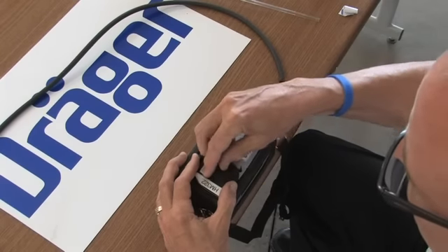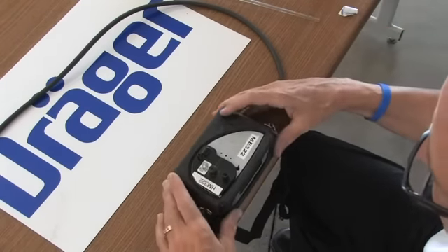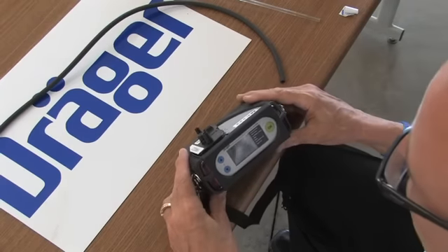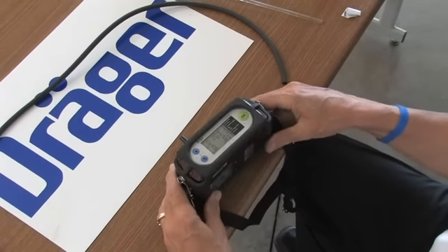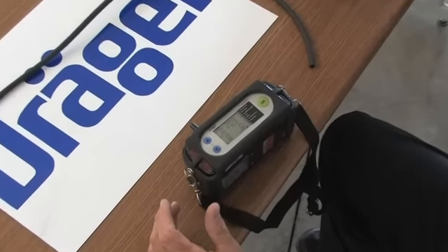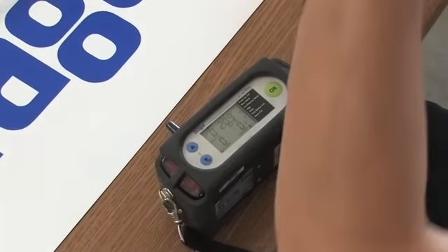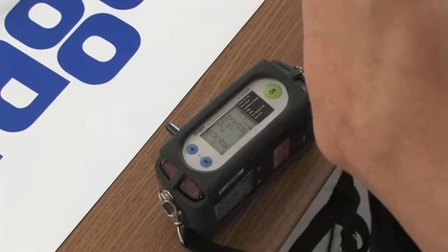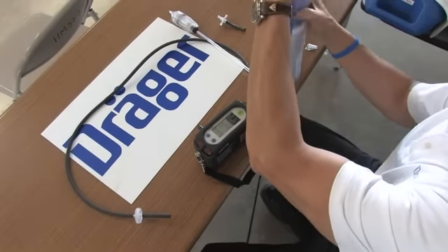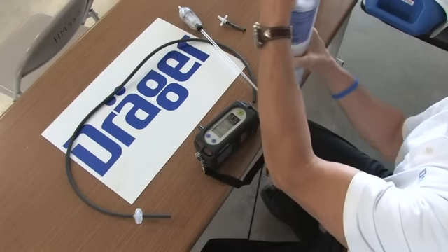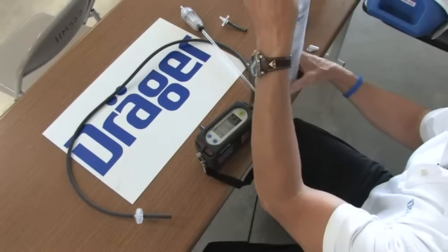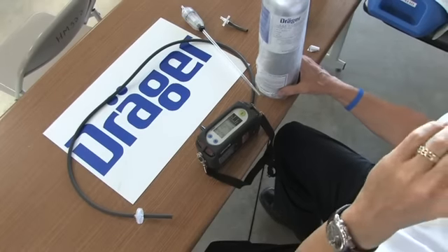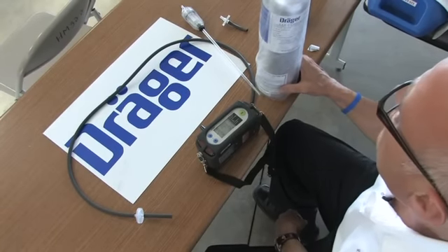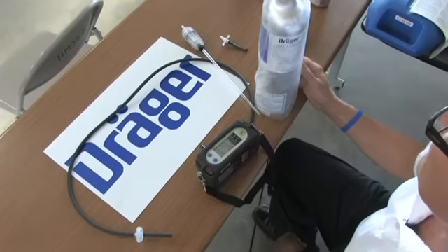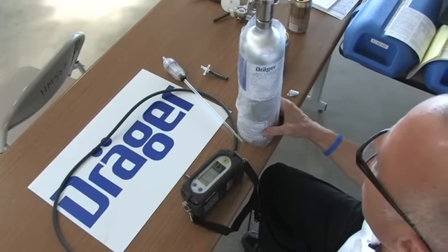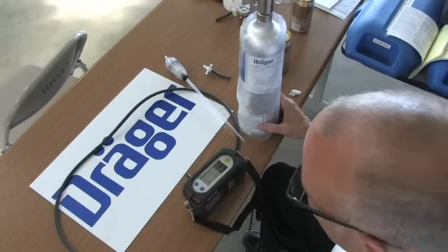Again, a knurled knob, just like on the MultiWarn II. And my pump is on and I can hear it running. So, I am now going to get my cocktail cylinder and my demand flow regulator. I'm going to attach my demand flow regulator. I'm also going to check my cylinder composition, and it's exactly what I need. The proper amount of methane, hydrogen sulfide, carbon monoxide, oxygen as well. And my contents are certified until May of 2011, so I know I have a good cylinder of gas.